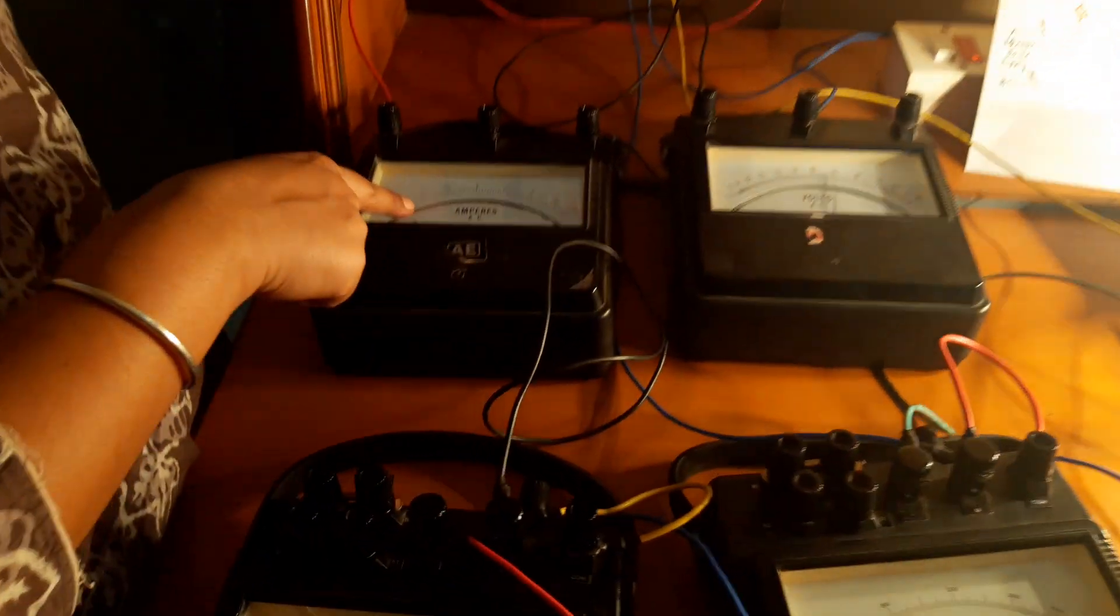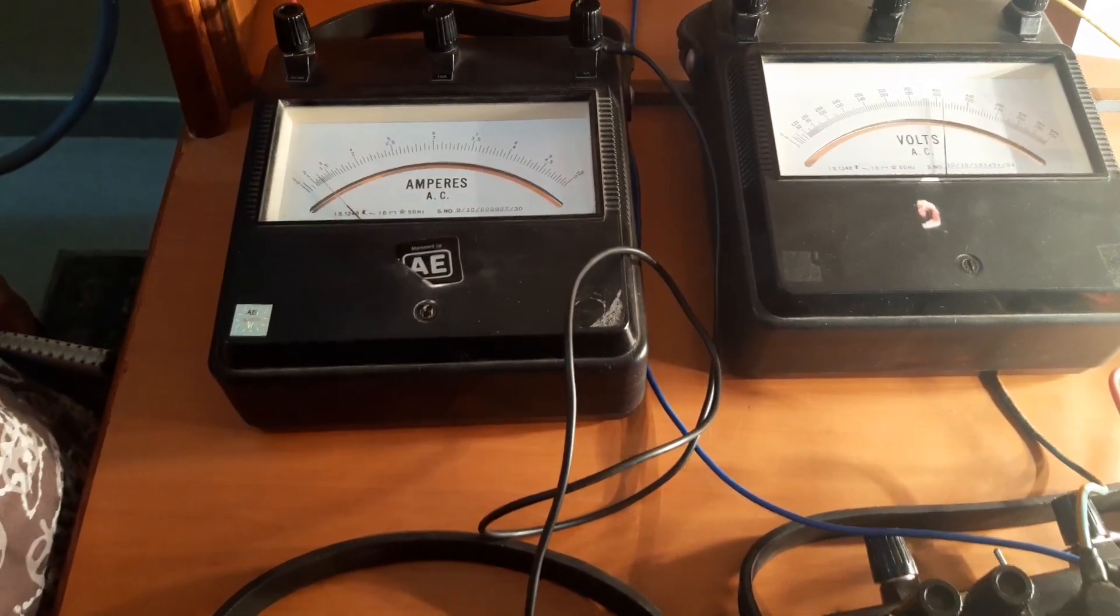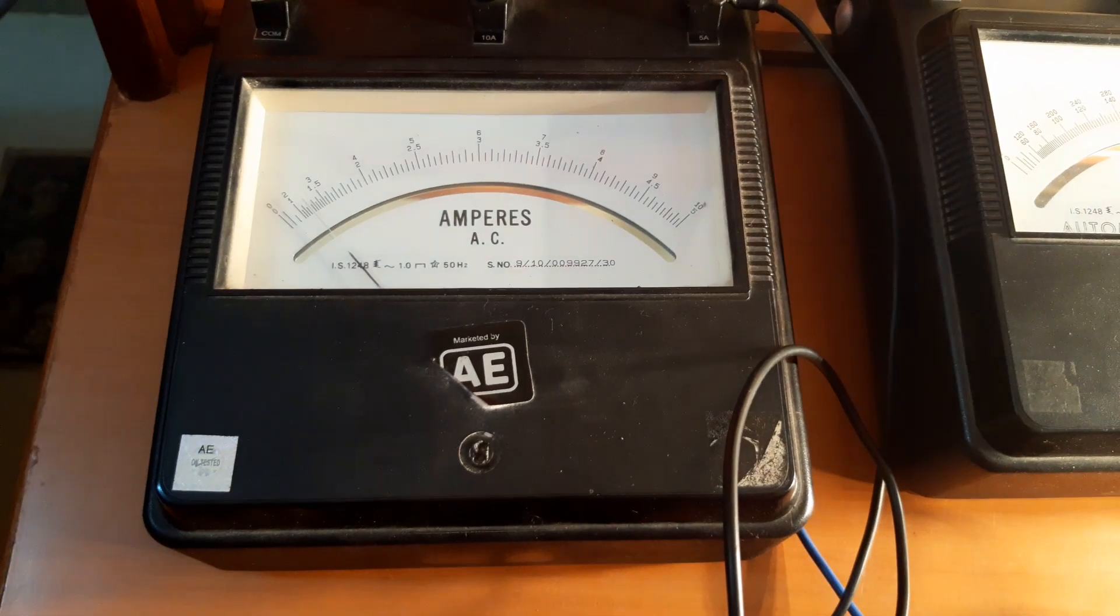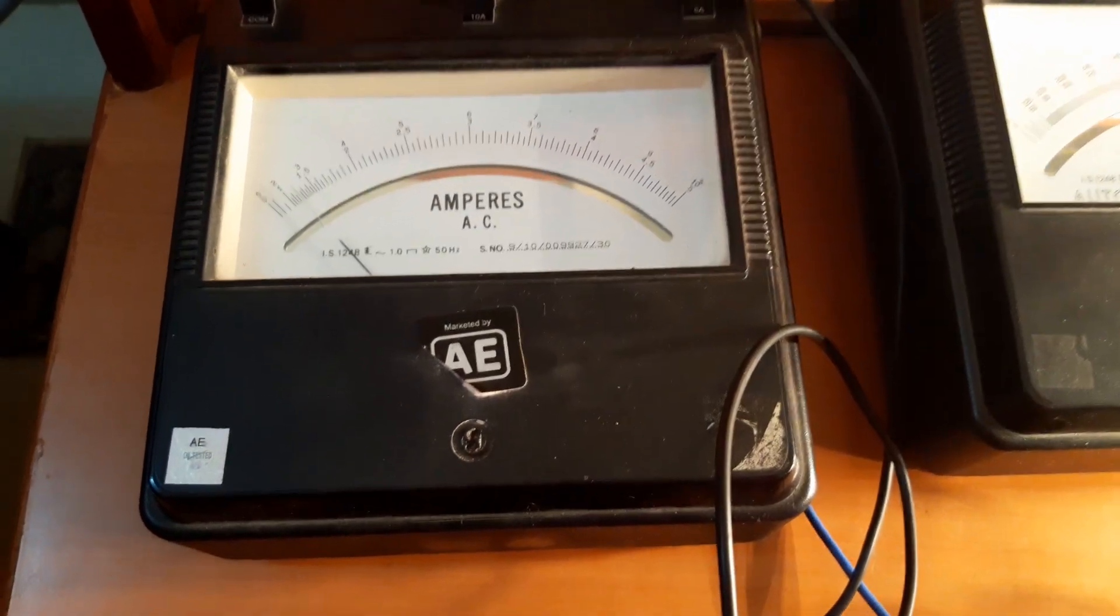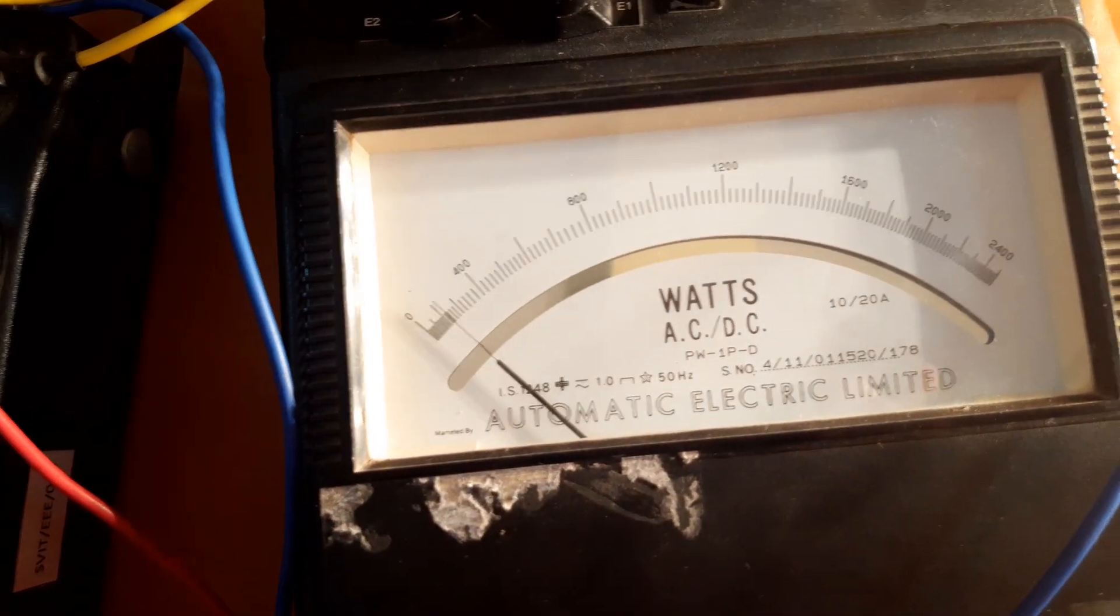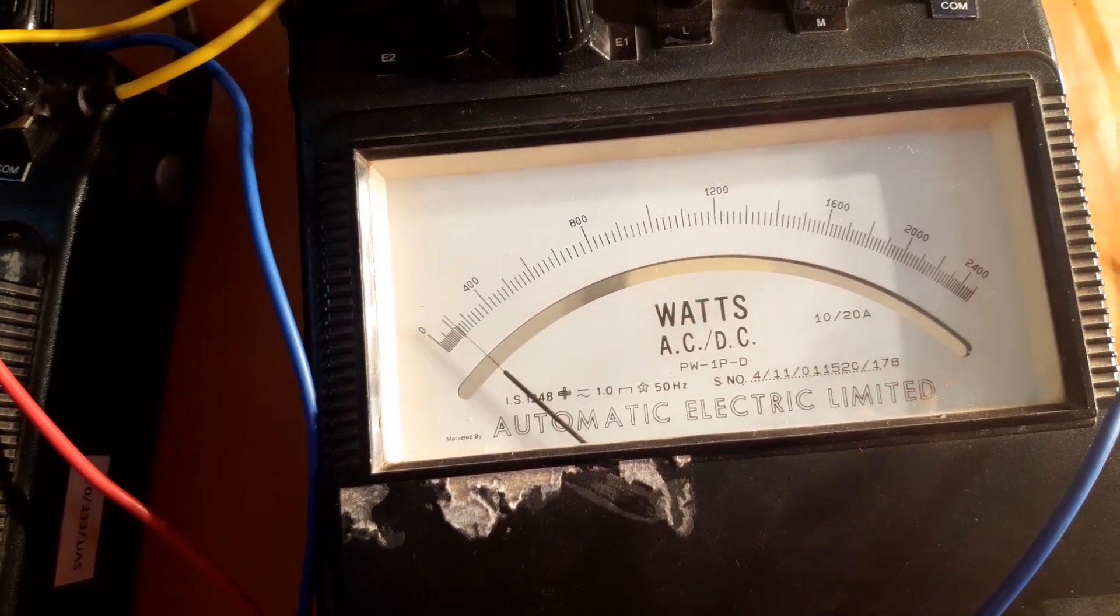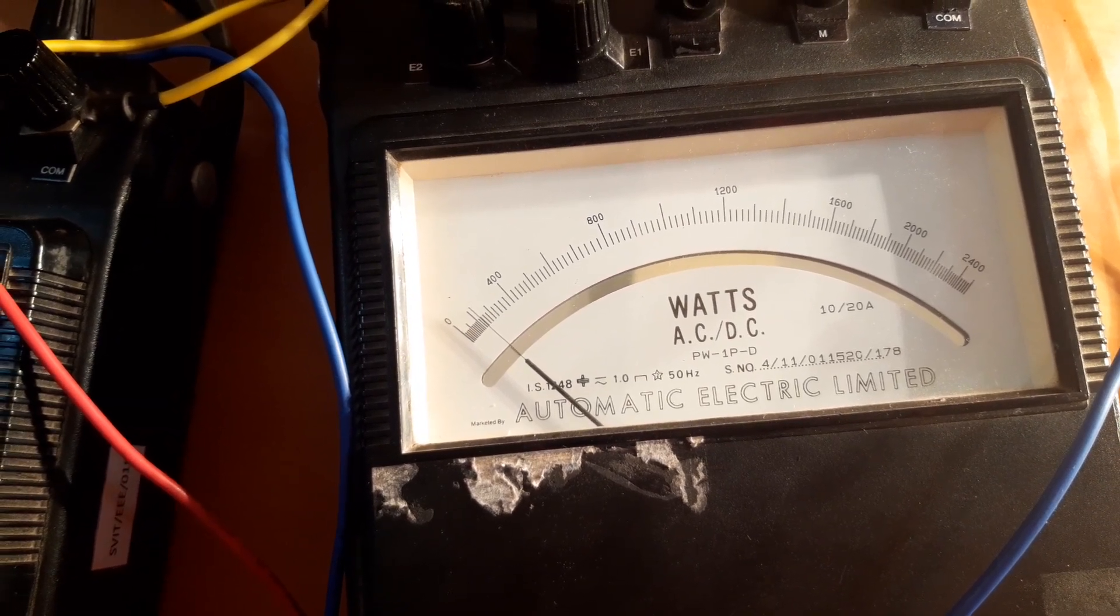The readings of voltage, current, and power consumed are being recorded in the meters. The ammeter is recording 1.2 amperes, the voltmeter is recording 408 volts. Wattmeter 1 is displaying 260, multiply it with the wattmeter constant 2. Wattmeter 2 is displaying 160. Again, multiply it with the wattmeter constant 2 before you tabulate in your tabulation column.